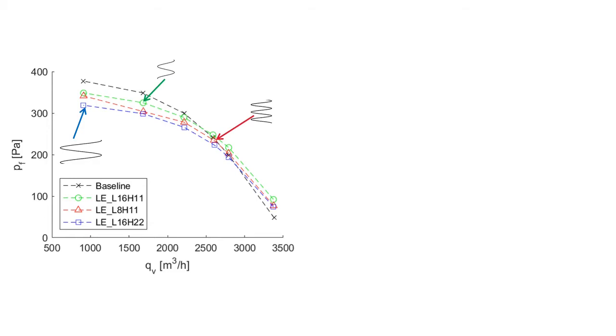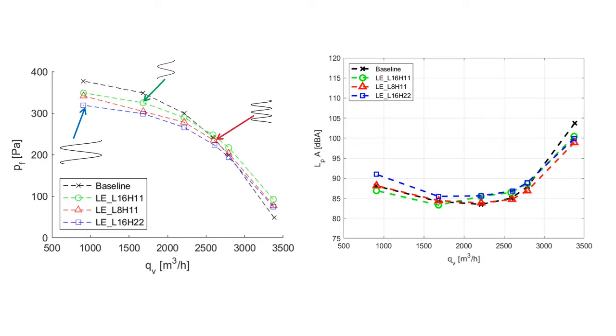We can plot the specific noise. Specific noise takes into account the pressure changes. It rewards pressure increases and penalizes pressure drops. If we do this, we see that leading edge serrations actually increase noise at most of the operating points.